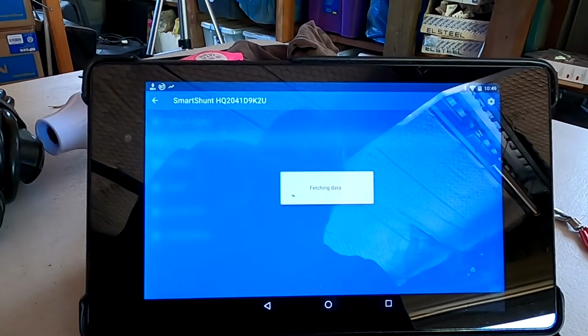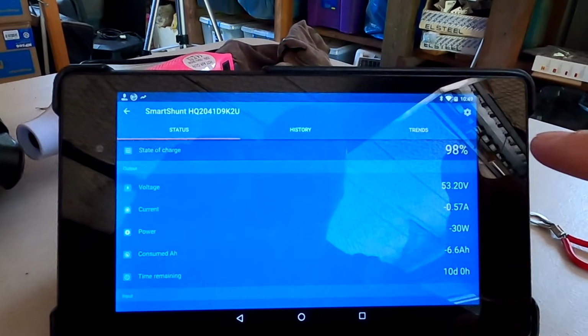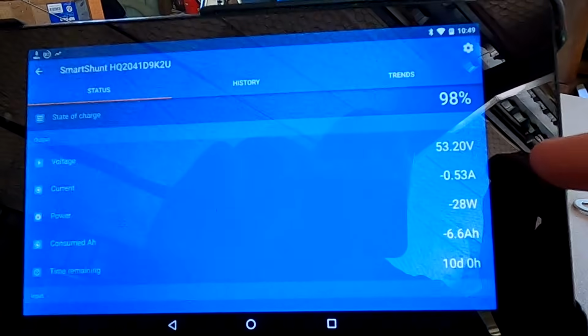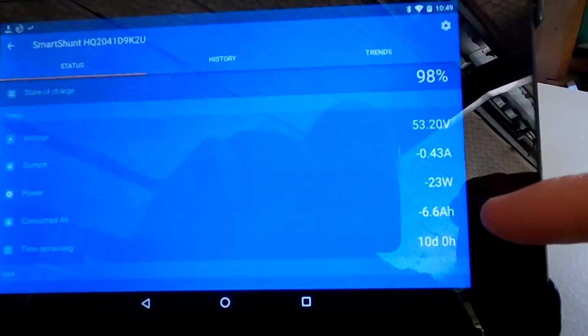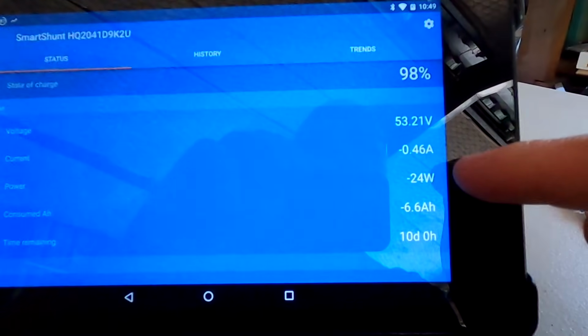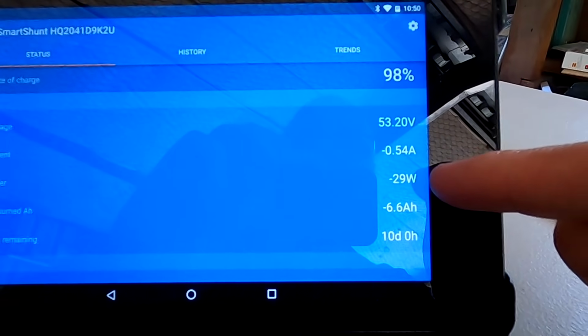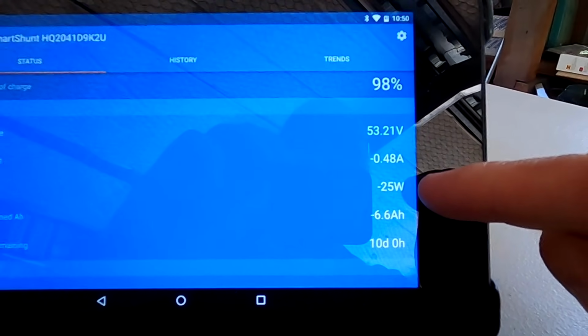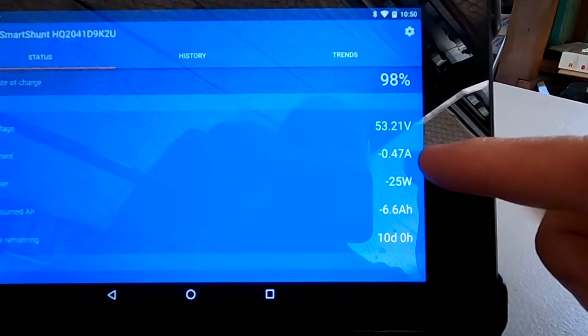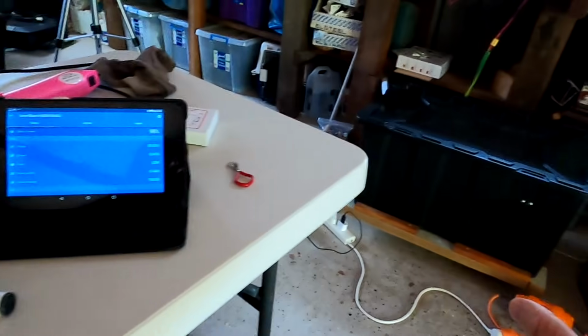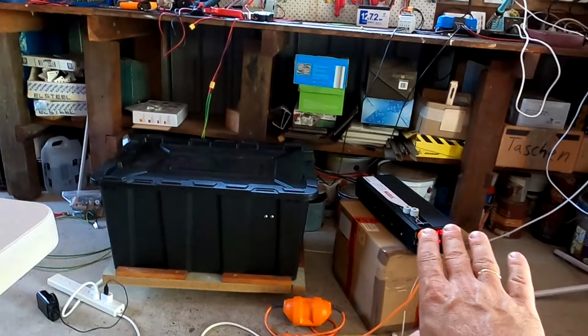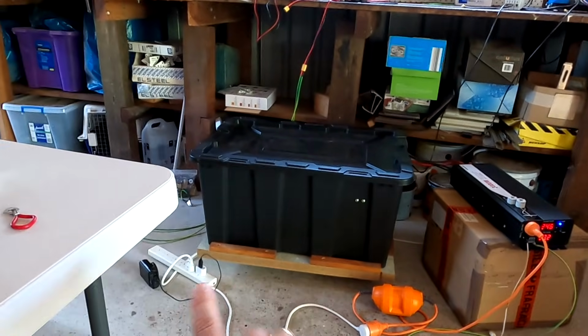It was on 100% last night, it is now on 98%, and we have discharged 6.6 ampere hours overnight by pulling about 20-25 watts from the battery. So half an amp, I'd say. The battery has been discharged with half an amp overnight from the standby of the inverter and some very little load — charging the camera.